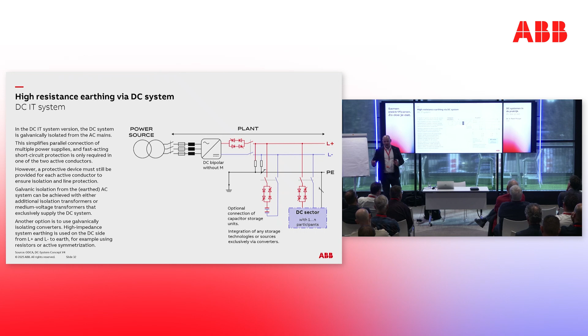The last system that's very interesting, with two variants, is using a midpoint. Using a midpoint gives you a big advantage, because instead of, for example, 800 volts, you can split it to plus 400 and minus 400. But there are again two ways you can do that. You either say, OK, I have plus and minus, but the midpoint is not used as loadable. This is nice, because you don't have to think about balancing. If you load the midpoint, you will have equalizing currents flowing in your midpoint, and you need to somehow balance it—so you need one more device. But this is a little bit connected to the voltage levels that are available.